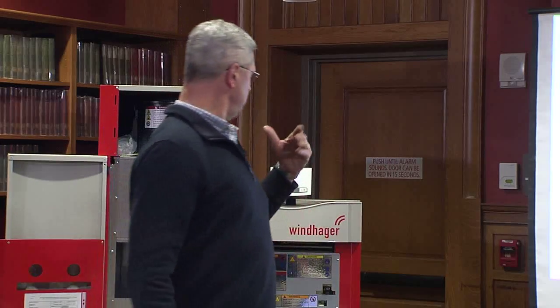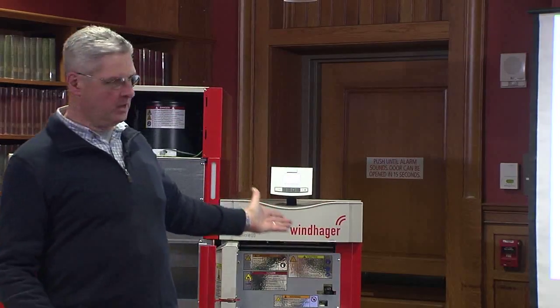So somebody who had an 80,000 BTU home, where the heat loss required 80,000, had an 80-gallon tank. If somebody had a 120,000 BTU requirement, they had a 120-gallon tank. Okay, these are well-insulated tanks, and they'll run as long as your heat or hot water requires. So that's thermal storage. Just so you know, these systems often work in conjunction with thermal storage.